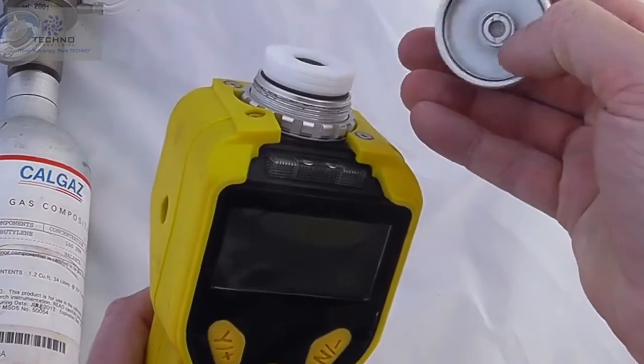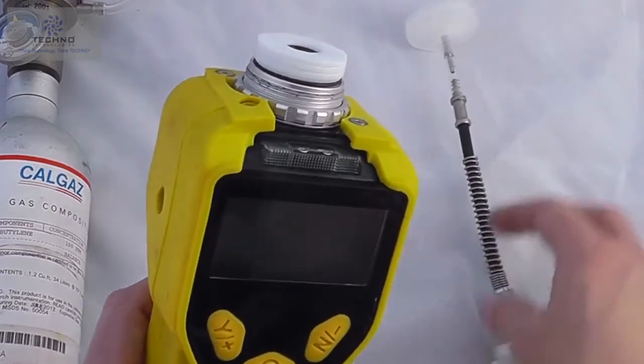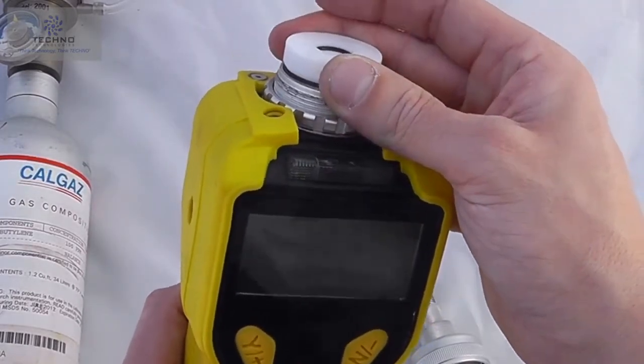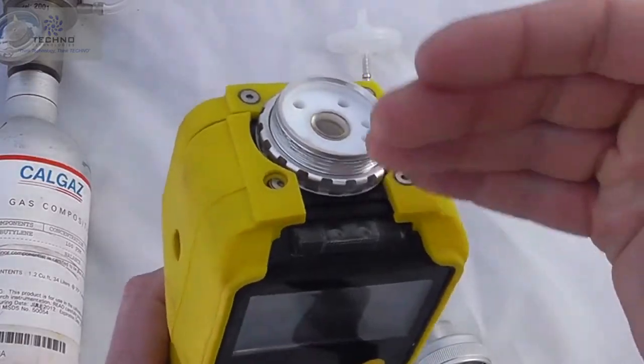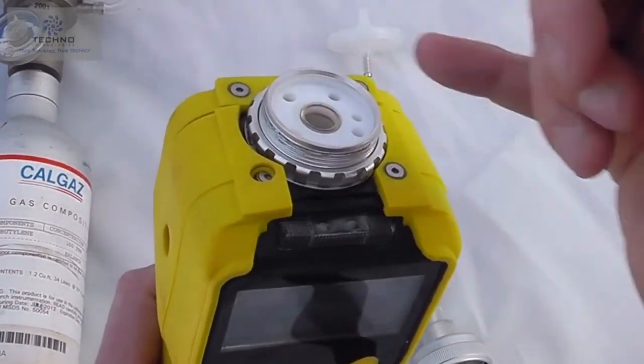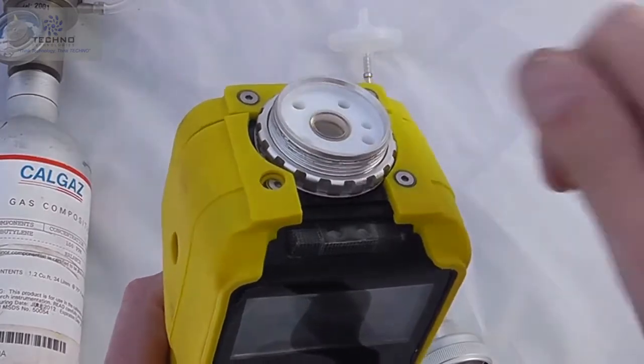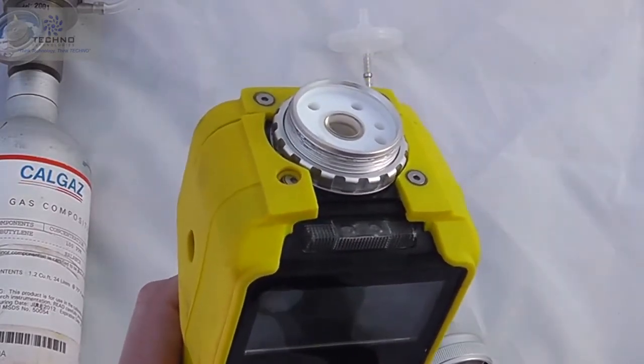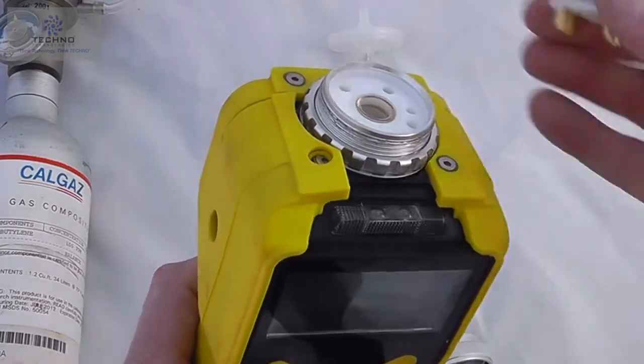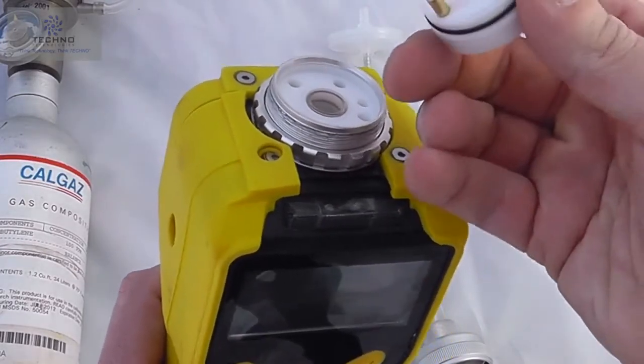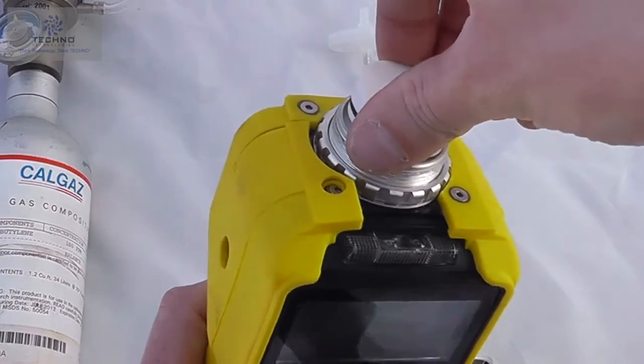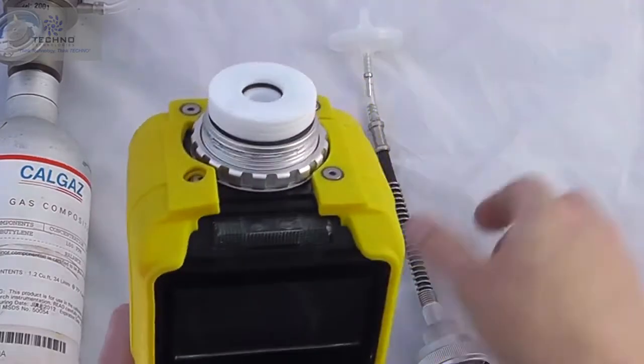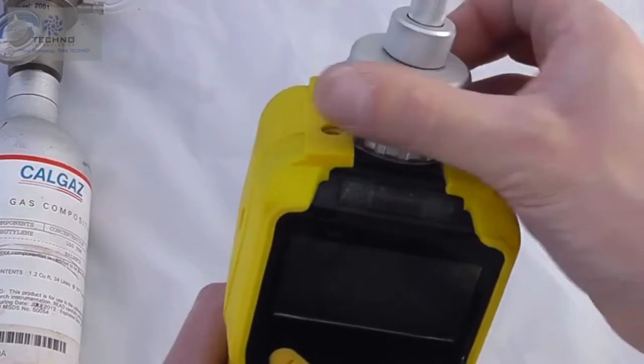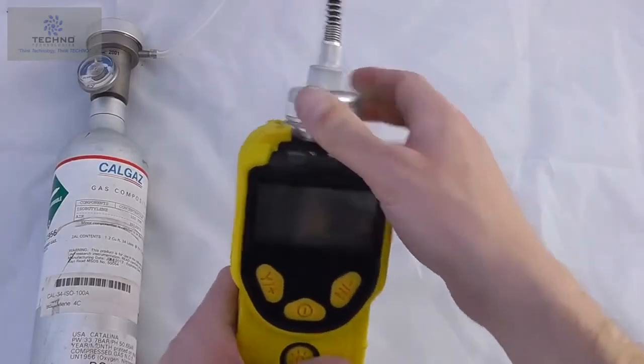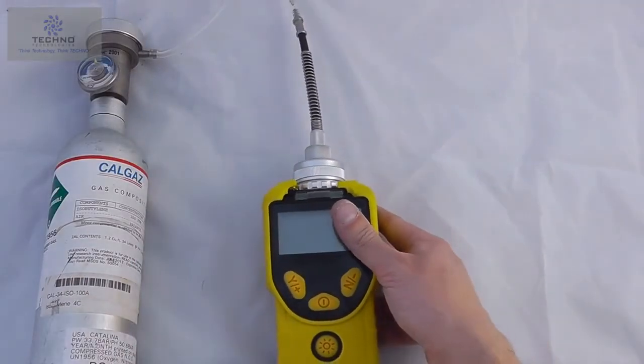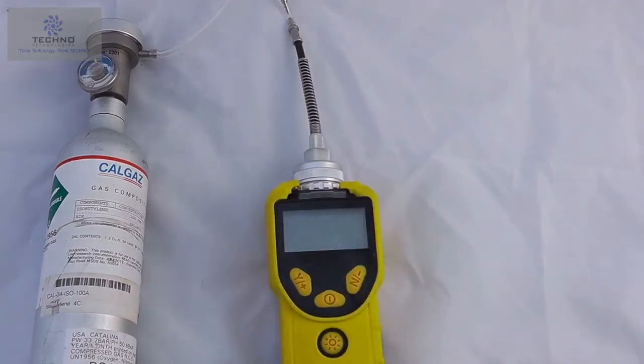You can see there is an additional level of filtration in there. We can remove the sensor block from the top of the instrument, and we can then see the lamp is now exposed. It's important not to touch the surface of the lamp, but use the cleaning solution that's been provided by RAE Systems. And then we want to reattach the sensor block, again making sure we don't touch the sensor block at the top here. We can replace the sensor block section, clips back into position, and then reattach the probe. And that gives us a full synopsis of the MiniRae 3000 series from RAE Systems.